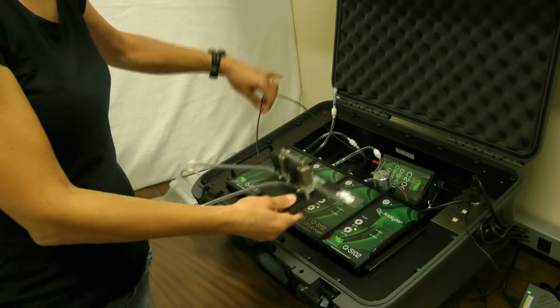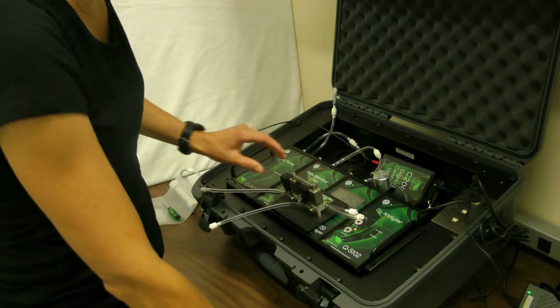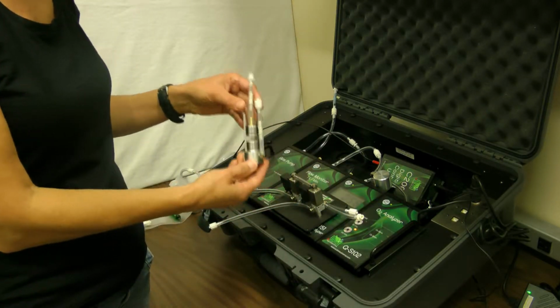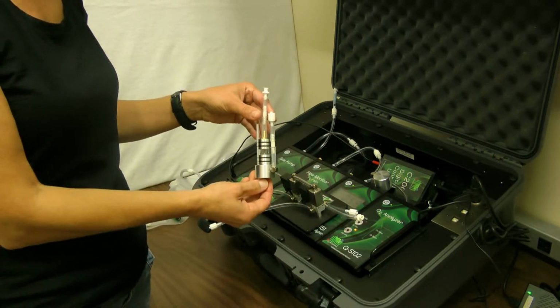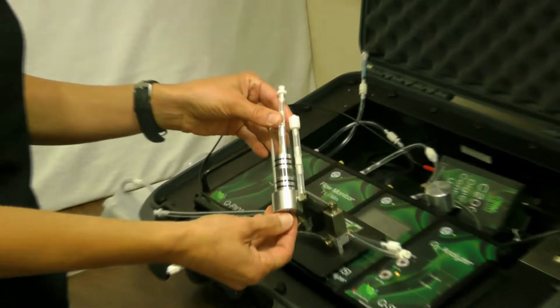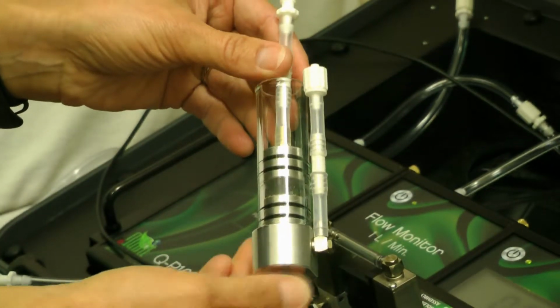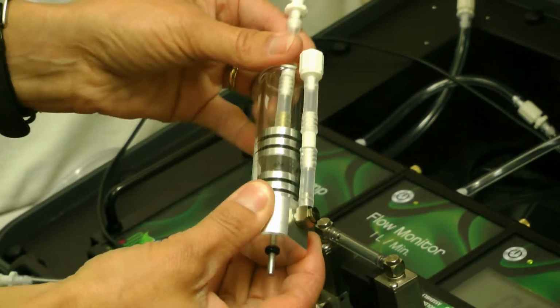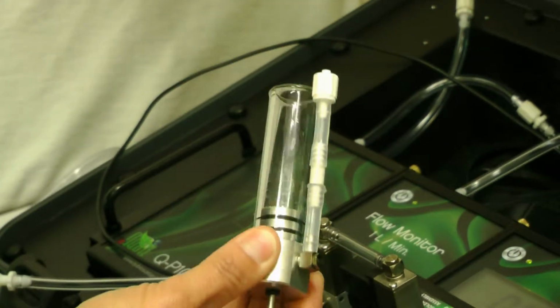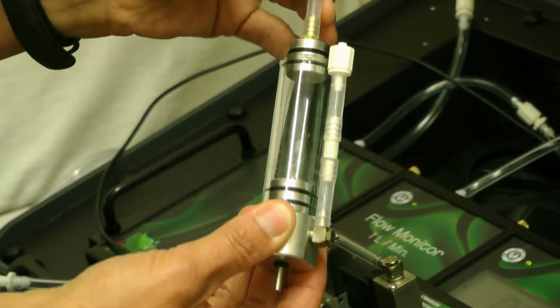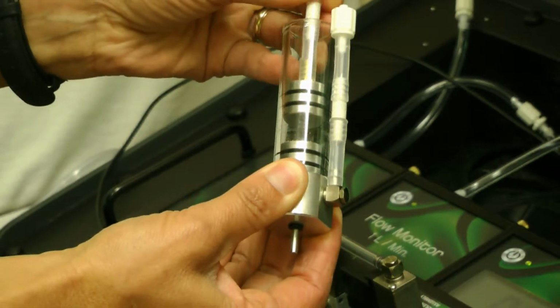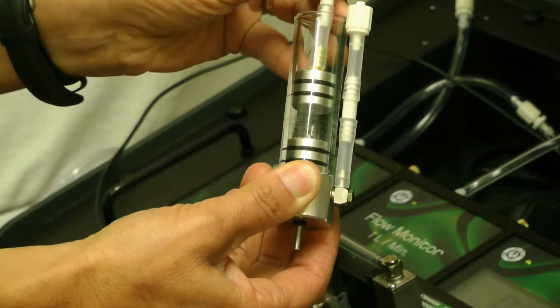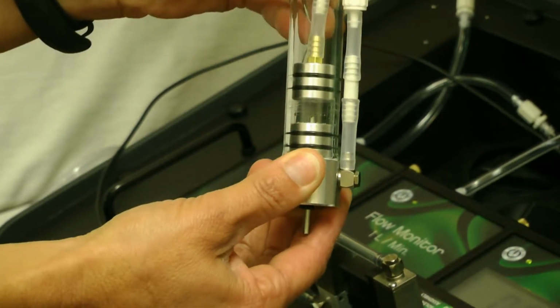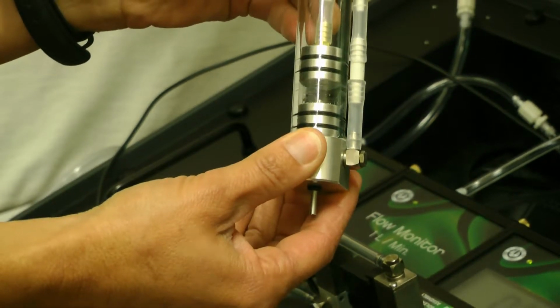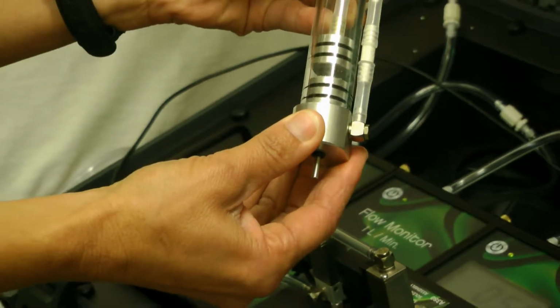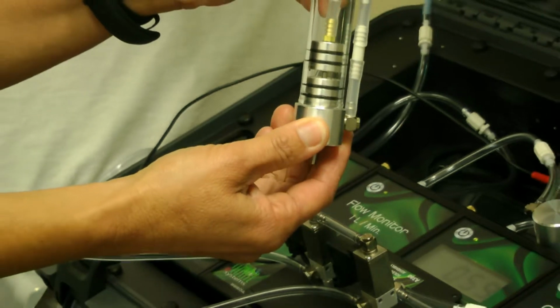So once this is assembled here, you can then attach the chamber. The chamber that comes with the Enhanced RP1LP package is a variable volume chamber. It's a glass chamber with aluminum end caps. One of the end caps can be completely removed like this, and this is the one that you can adjust. With it, you can adjust the volume of the chamber. So if you have very small samples, small little fruit flies, you can reduce the volume to very small.